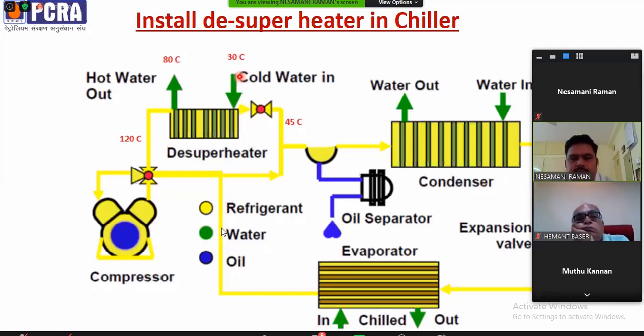But during the early mornings, what happens? Solar will not be sufficient to provide the heat, but in the early morning, hot water requirement is very high. So they used to supplement the solar plant with normal electricity heaters. They have replaced those electricity heaters with this one because the chiller runs the whole day. The hot water recovered from this desuperheater is sent to the room bathroom water supply. So they had very good savings.